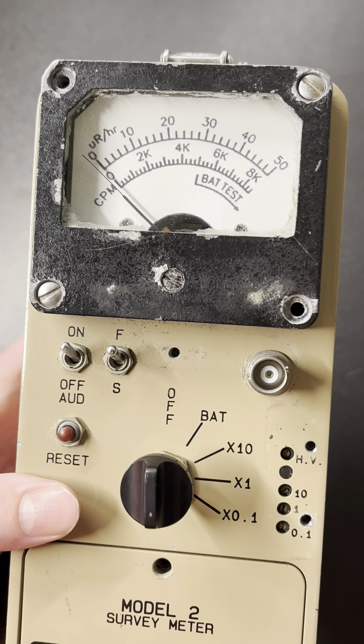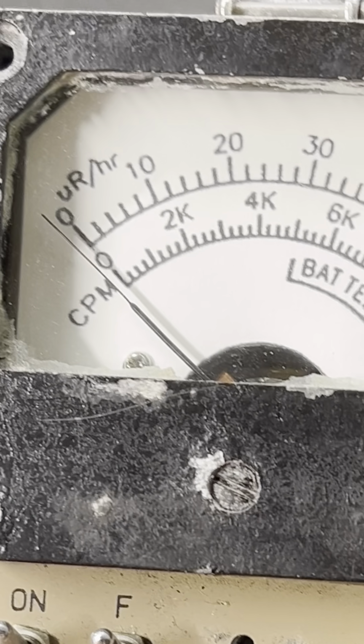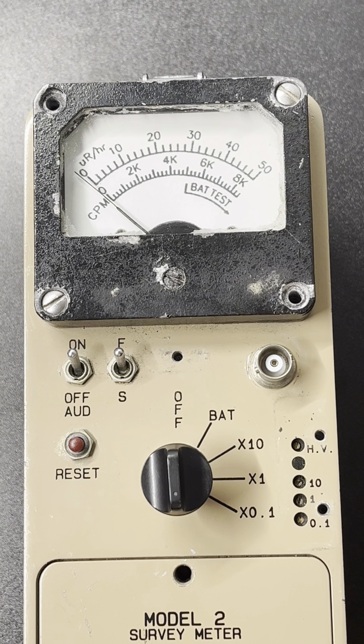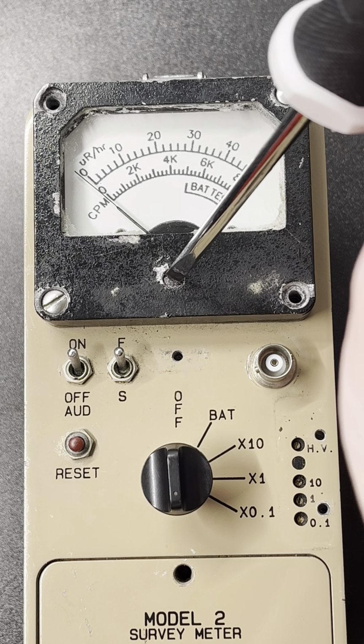Next, I calibrate the analog gauge by ensuring that the needle is aligned with the 0 position on the faceplate while the instrument is turned off. I can change the 0 position by inserting a screwdriver into the bezel.